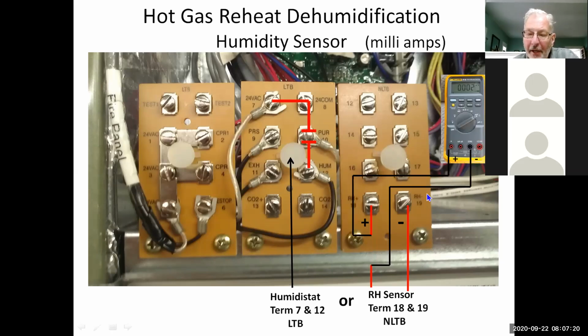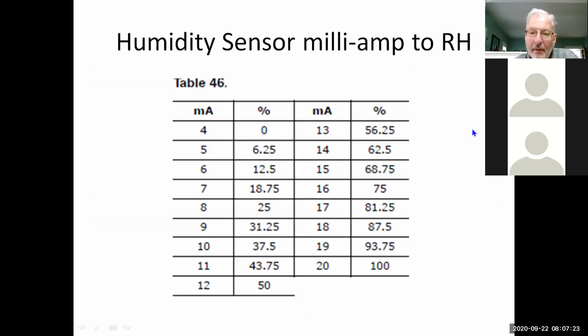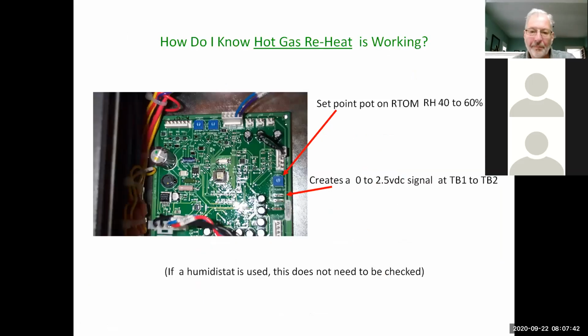You can check the dehumidification by taking a reading here. It'll tell you what the value is. So if I have 5 milliamps, I have 6.25% relative humidity. If I have 17, I have 81. So you can get a humidity reading if you're using a Trane American Standard control. You can set the dehumidification units with this potentiometer right here. All the way counterclockwise is 40%, all the way clockwise is 60%. So you do have that range of 40 to 60%. You can read the signal here too, which is 0 to 2.5 volts DC to tell you where you're at.